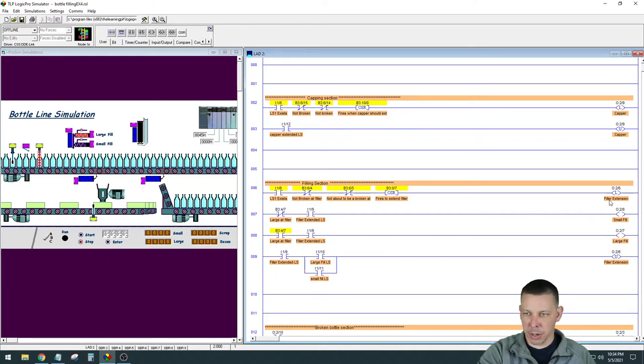And it's not going to go back true, even if all this stuff before this one shot is still true, because it happens really fast. It's not going to fire the extension to go back out again, because the one shot only goes when you've gone from a low to a high. You have to be on a rising edge. So even if this didn't change state and these two are still true, this extension is not going to just keep jumping in and out and in and out. I saw a lot of people with programs like that too, because this LS1 has to drop out or something else has to change. This one shot has to go low and then back high again to make it fire again. So hopefully that makes sense. You'll see it when I run it here in a second.